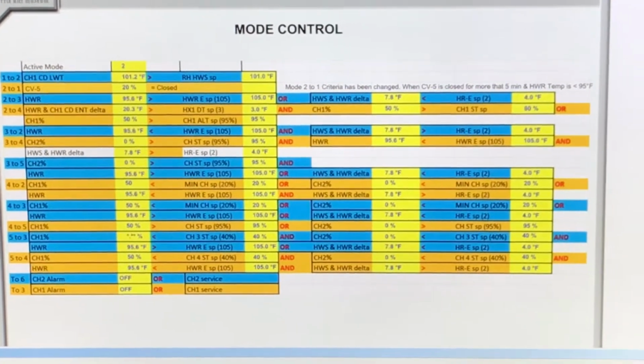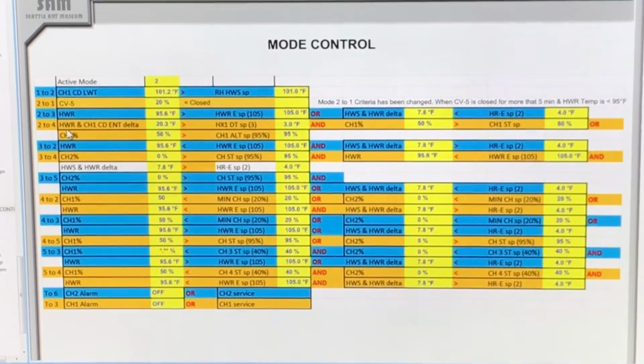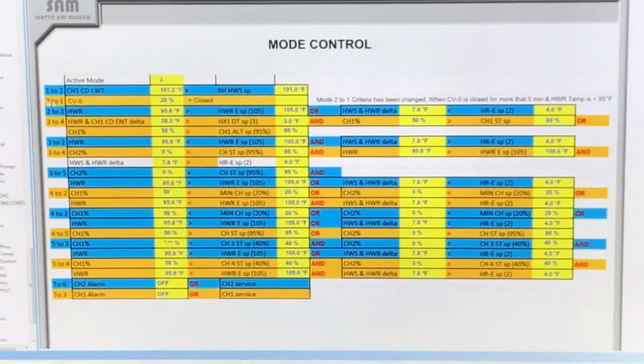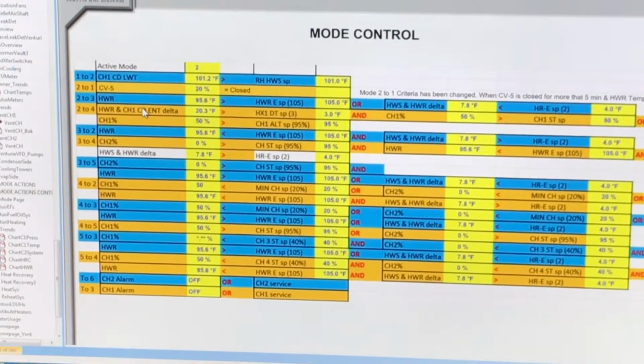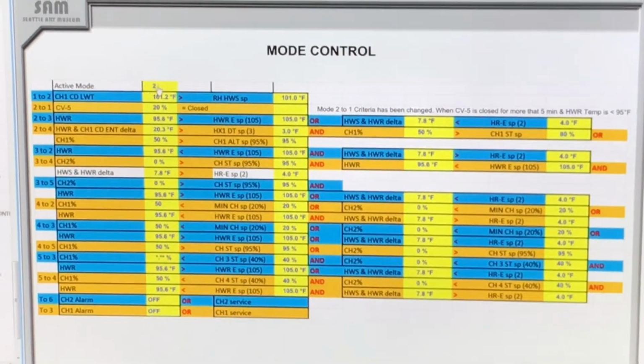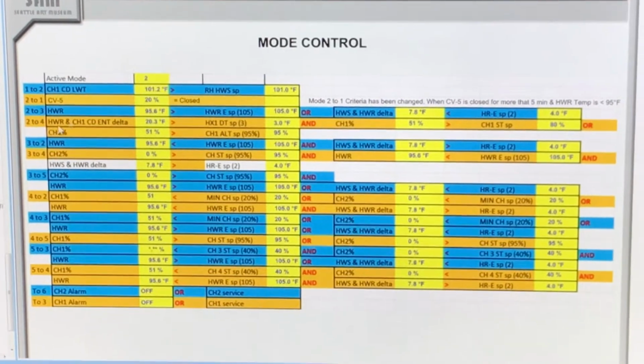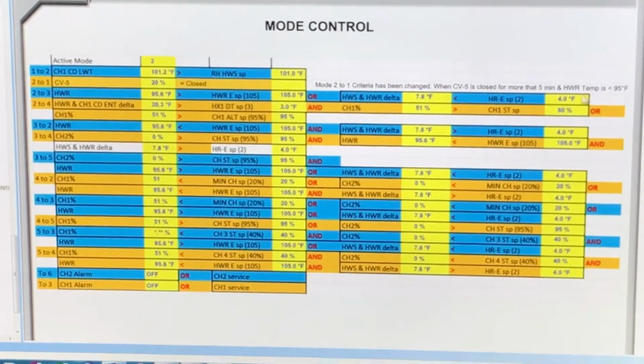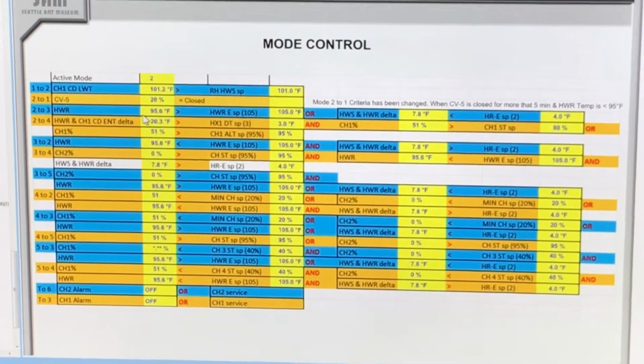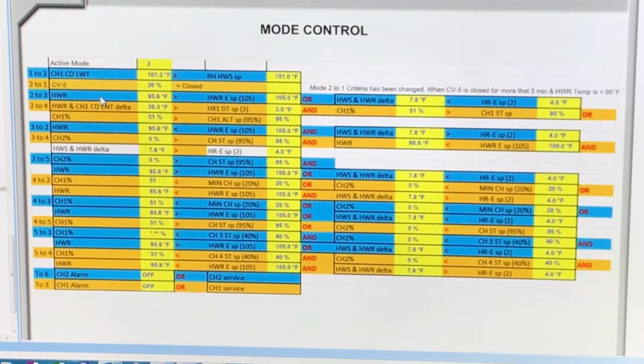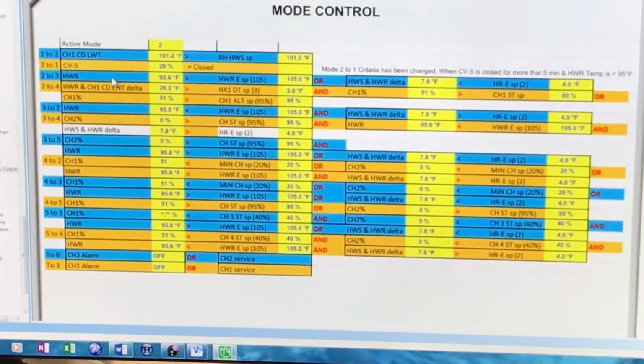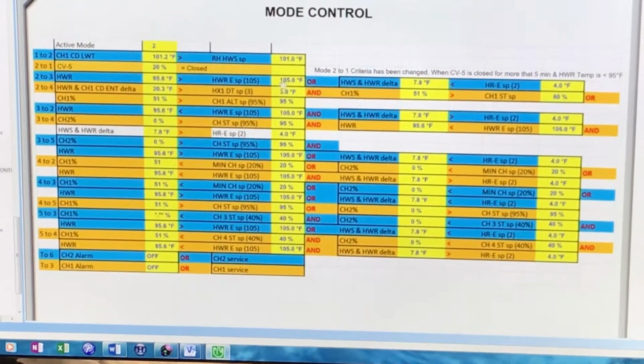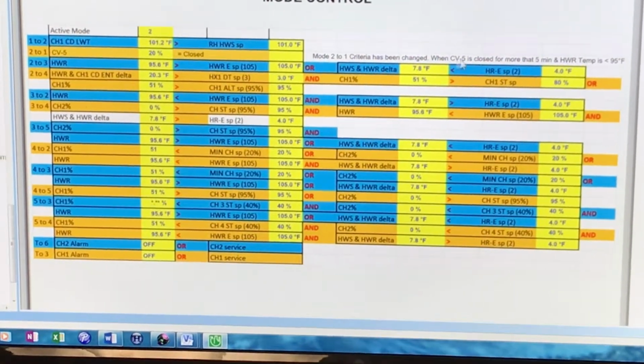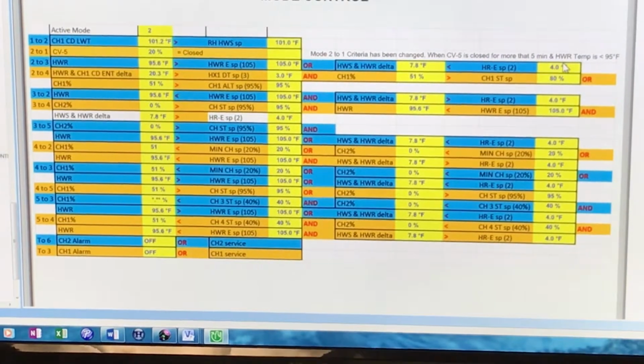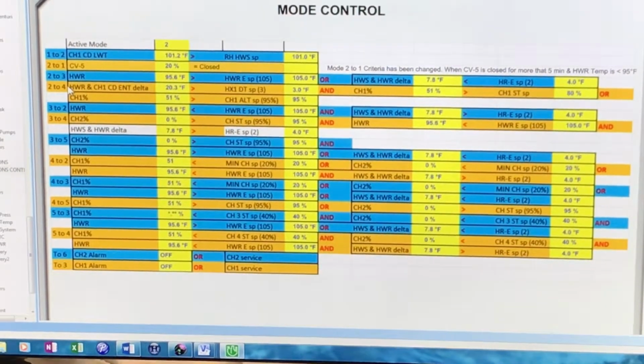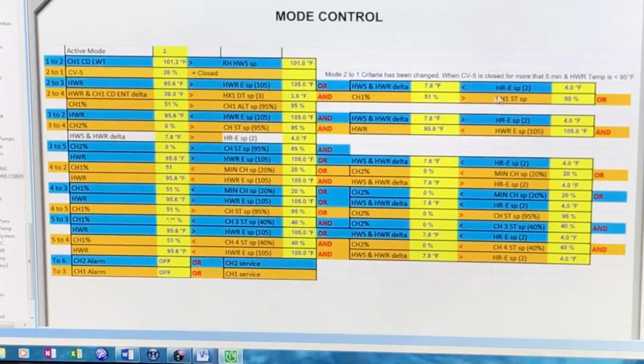So basically, let's go through the next one. It's the same type of scenario. We did 2 to 1, 2 to 3, and 2 to 4. That's the only way it's going to change to a different mode, if any of these come true. It doesn't matter if it's an "and" or an "or." If this comes true or this comes true, it's going to change to mode 3.